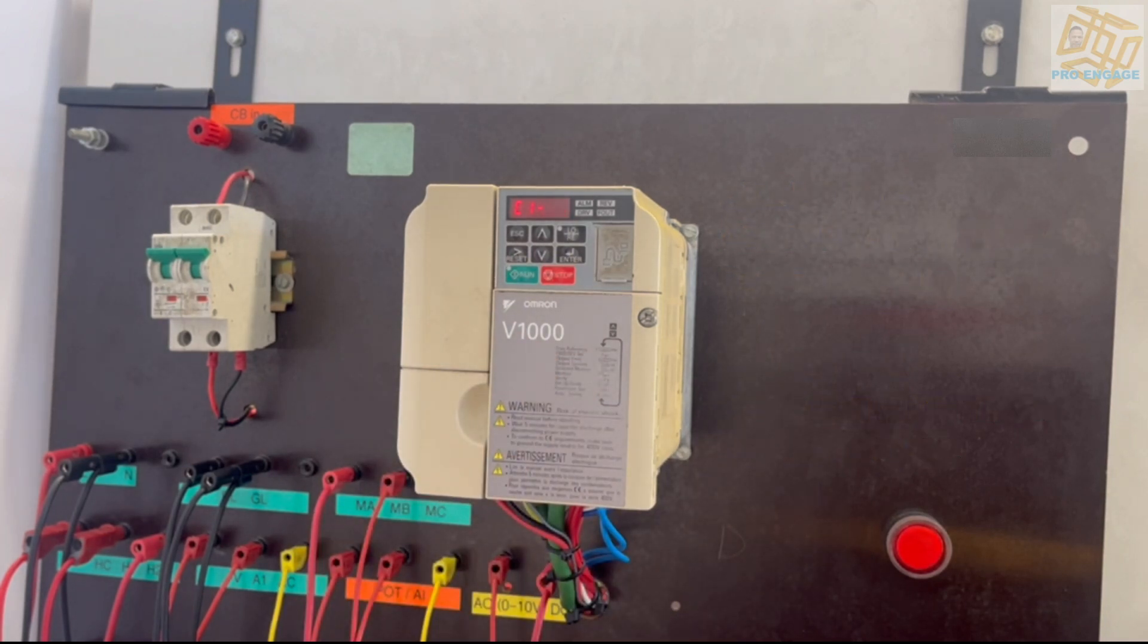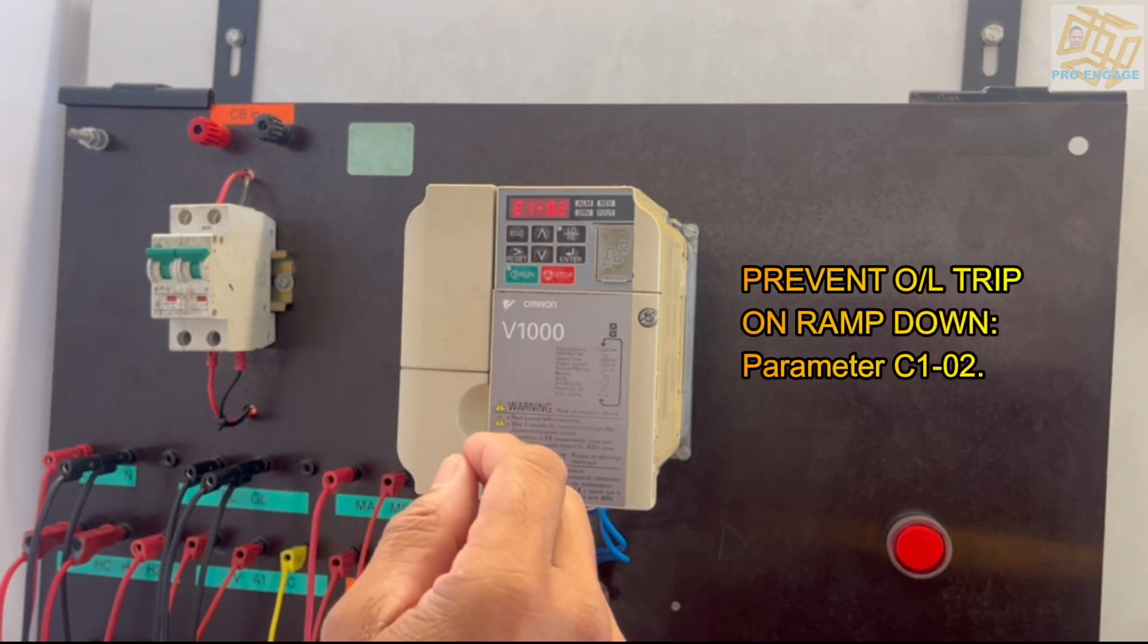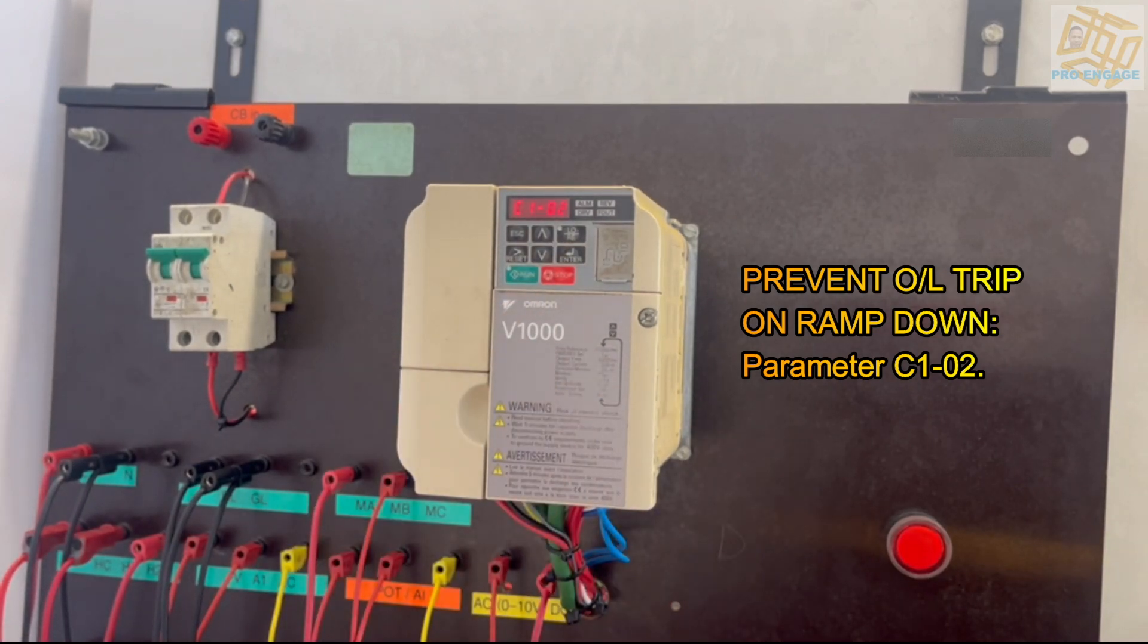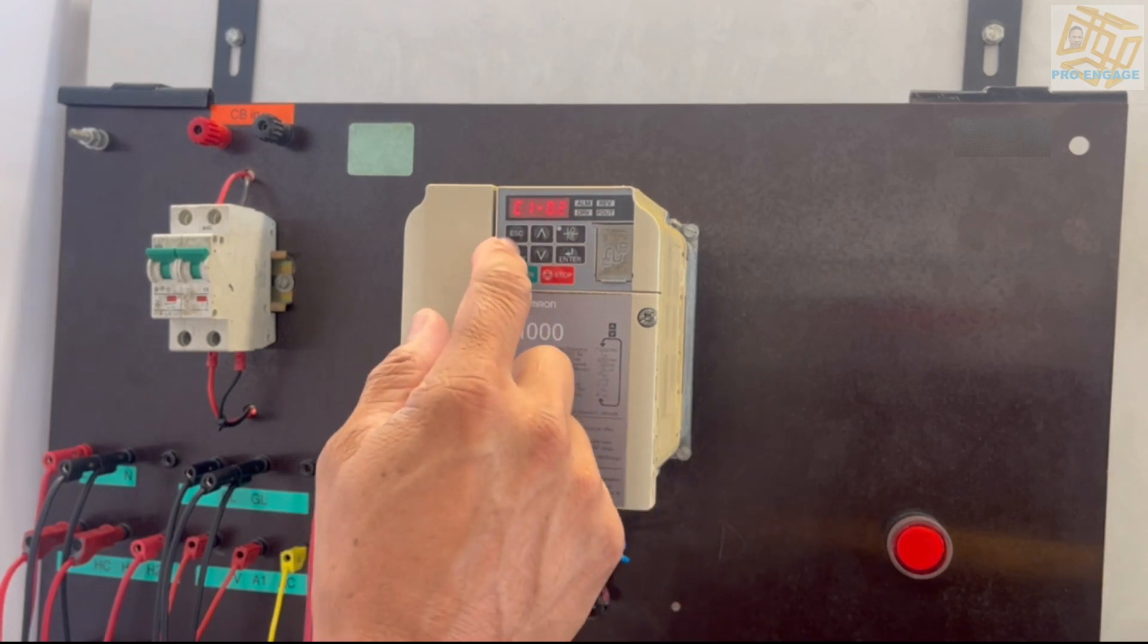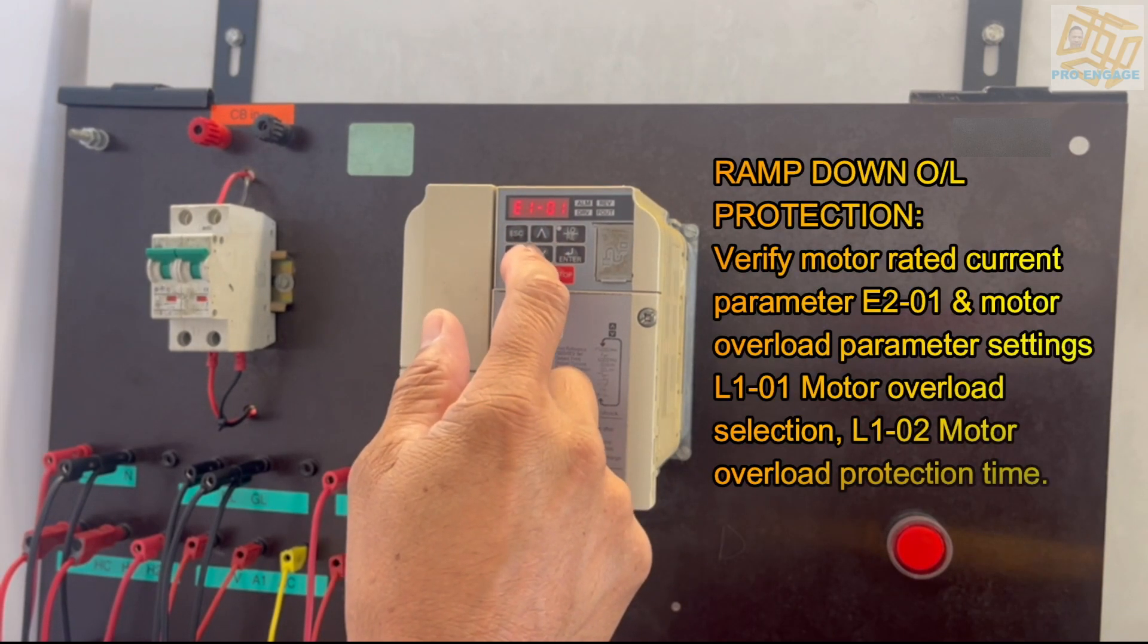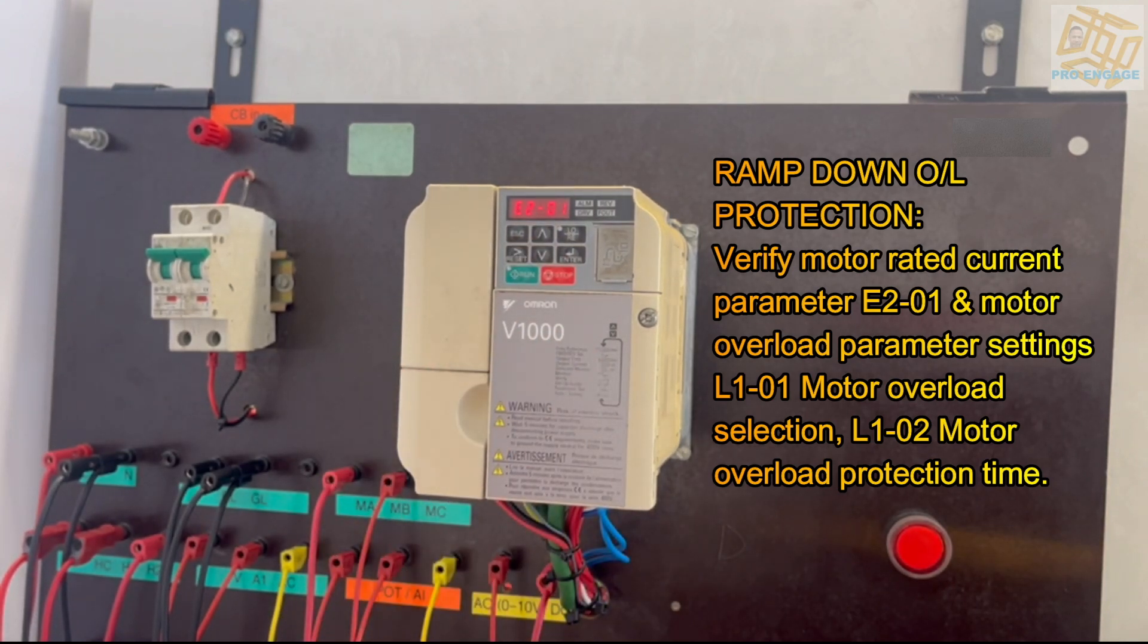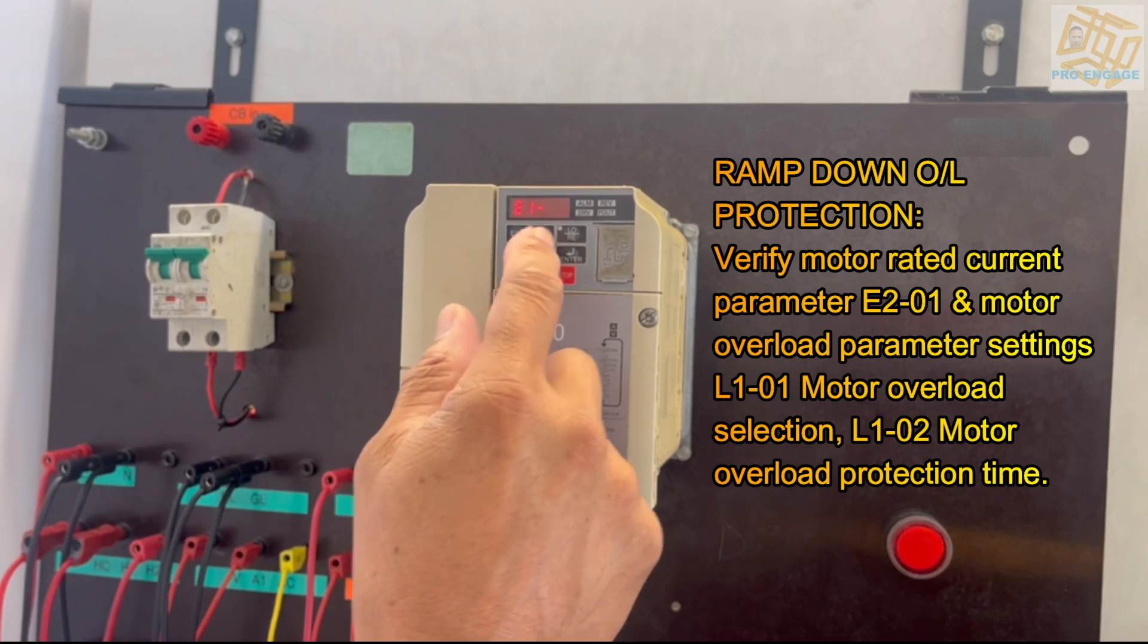The next parameter is prevent overload trip on the ramp down. That's parameter C1-02. You press enter after you've entered all parameters. The next parameter would be ramp down overload protection. Again, verify motor rated current parameter which would be E2-01. Put the parameters in the motor overload settings.